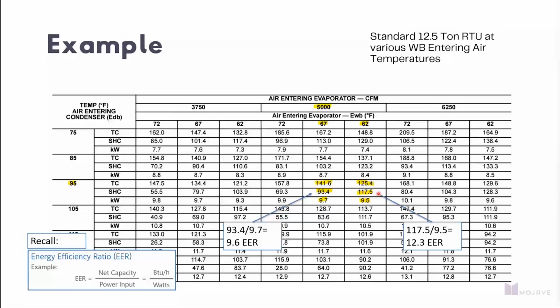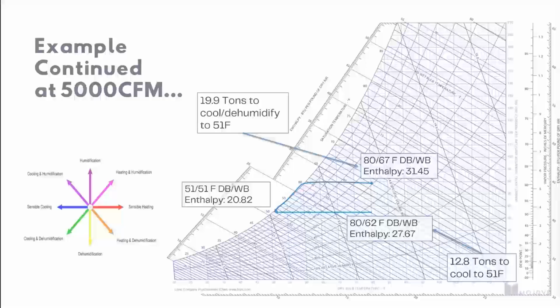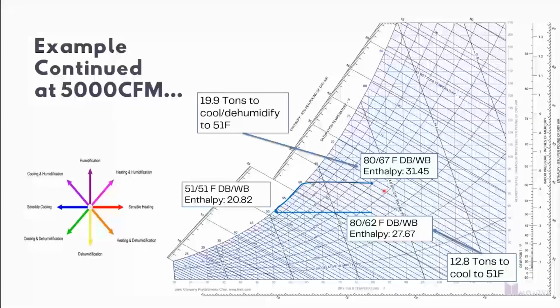Additionally, you get a higher effective capacity or sensible capacity out of this unit, and sensible capacity is really the temperature that we could feel in a space. So that's really what we're targeting from a cooling capacity standpoint, ultimately: the temperature that we could feel.